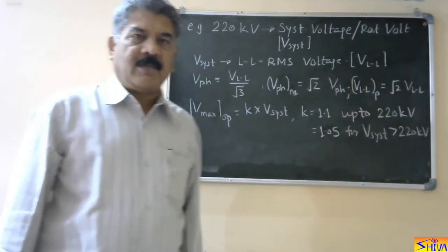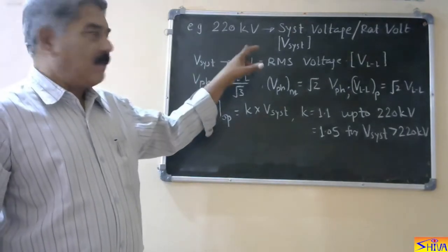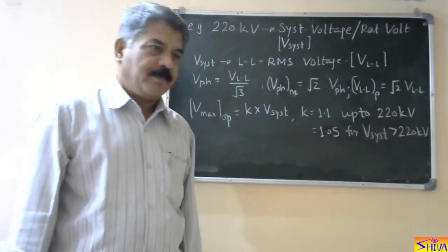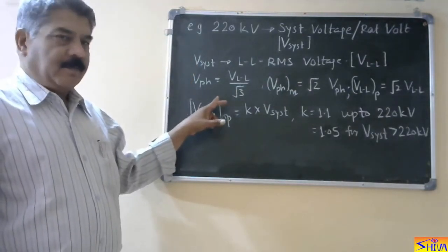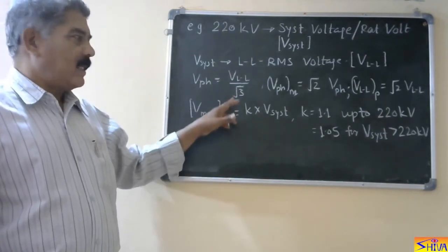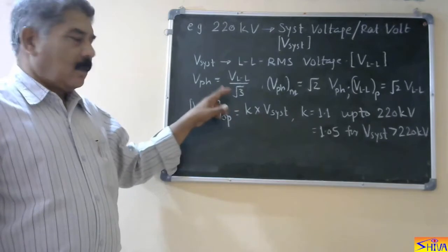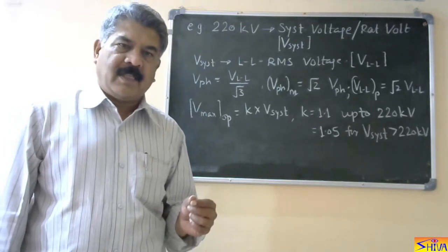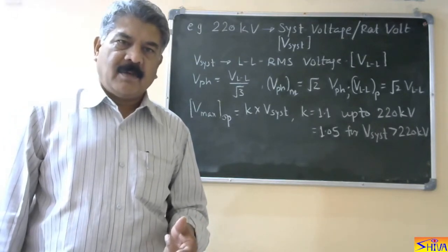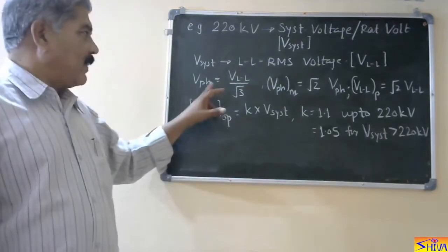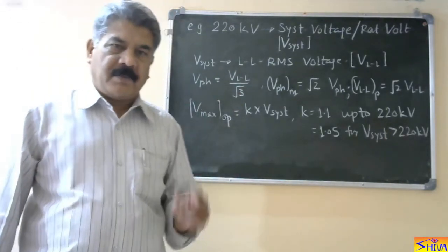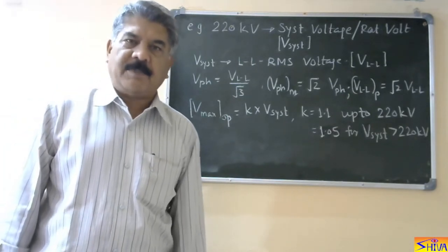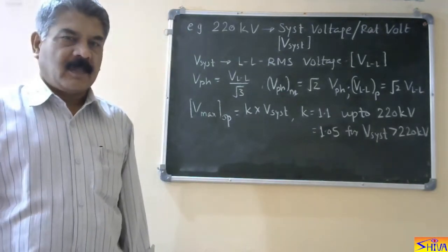Similarly, for a 400 kV system, that 400 kV is the system voltage — the rated voltage — and it is the line-to-line RMS value. The phase value is line voltage divided by root 3. In an AC system, line voltage is measured between two phases, such as AB, BC, or CA. Phase voltage is measured between a phase and ground — for example, phase A with respect to ground, phase B, or phase C with respect to ground.